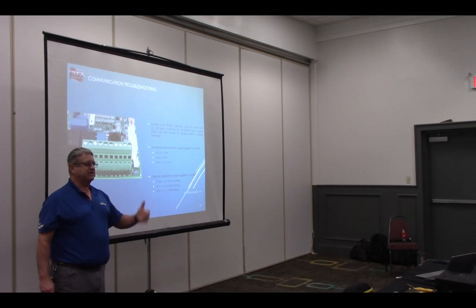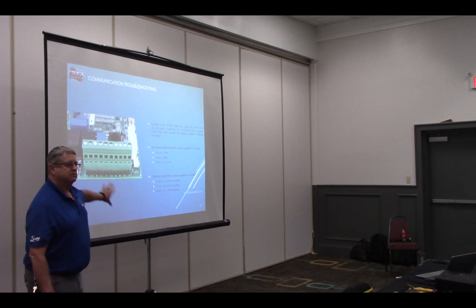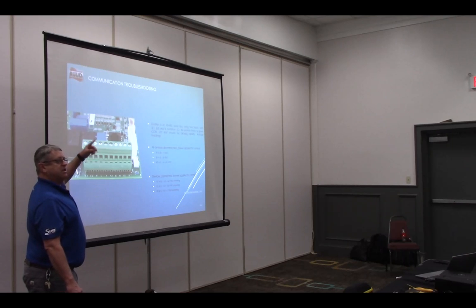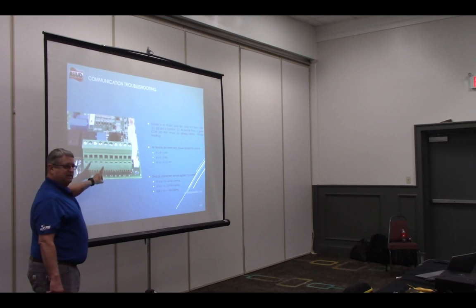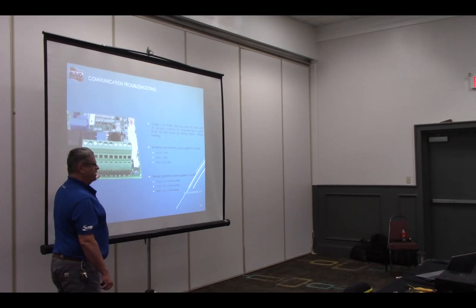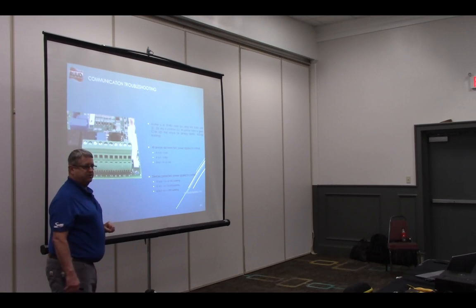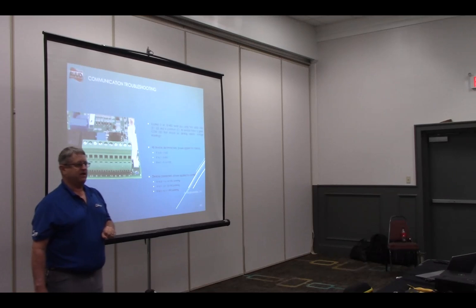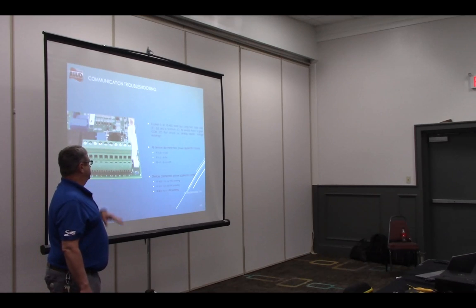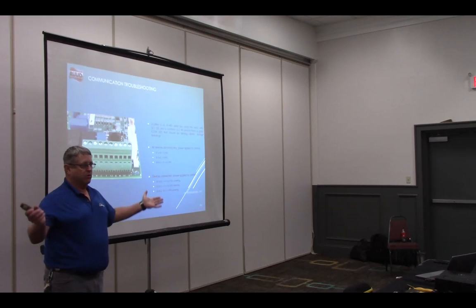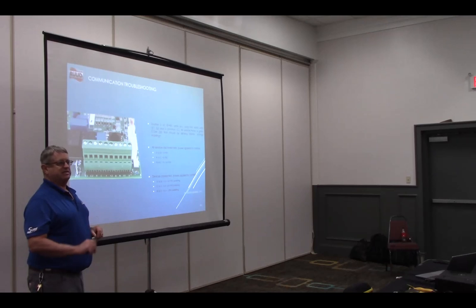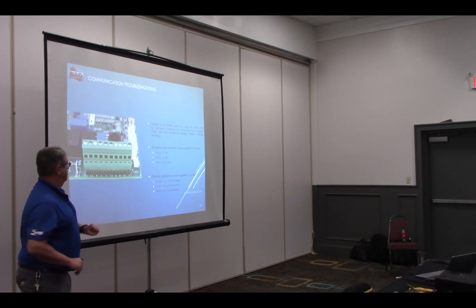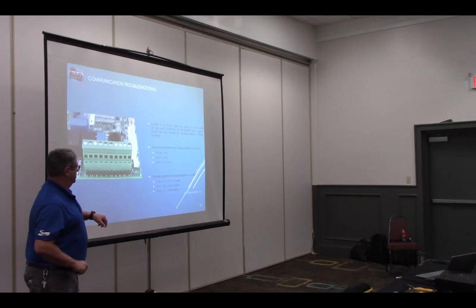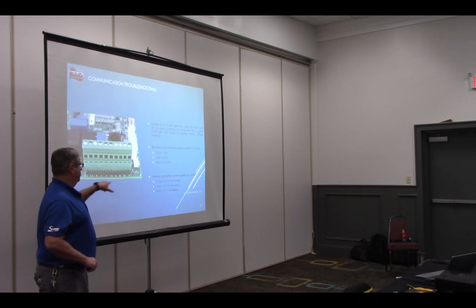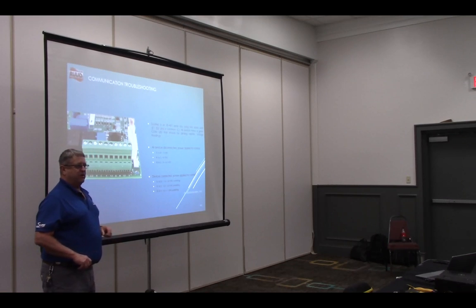Well, Mike, it says I have an outdoor communication error. Don't stop here. Now we're going to go indoors and do the same thing inside. Well, with E1 and E2 off, we're going to check and make sure that our board is good. Okay, let's say we find we have no volts DC between E1 and E2. What do we have? Bad board. So let's say that it all checks out though. Our board is good. And we connect E1 and E2 back up, and E1 and E2 checks out, but E1 into common has nothing on it.